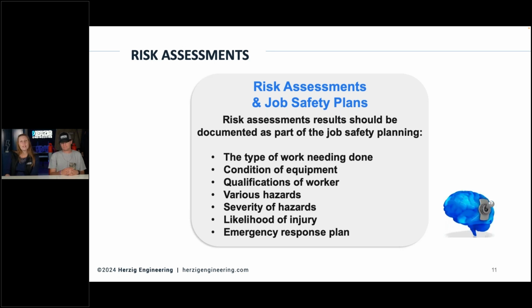And then the likelihood, so take that breaker example: if a breaker trips and you go turn it back on, but you didn't figure out why and help remove the chance of it tripping again, you could be closing into a fault. So the likelihood of that going wrong is higher. There's a lot of scenarios and examples we can go through, and we have in the past, but that's just to get you started thinking.